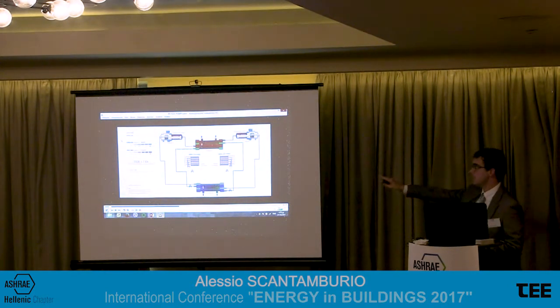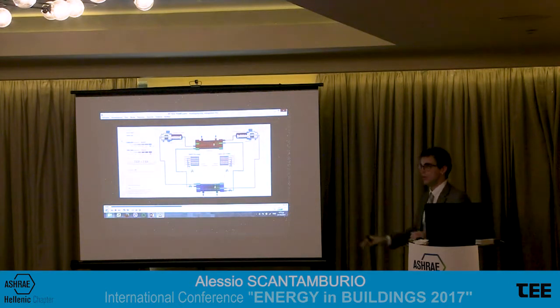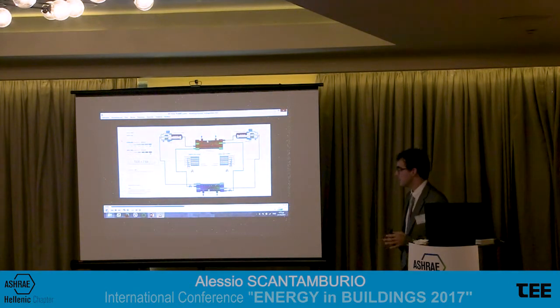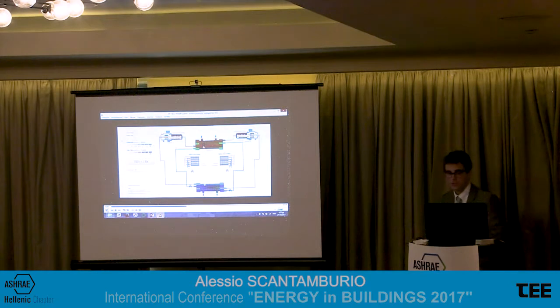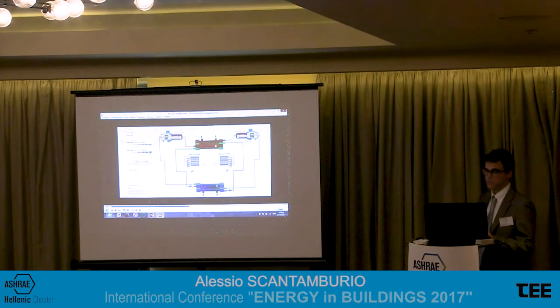Okay, this is a condition where a chiller with total heat recovery is okay. But the next combination is exactly the combination I was talking about before: a combination where the heating load is higher than the cooling load, in which a chiller with heat recovery is not enough.